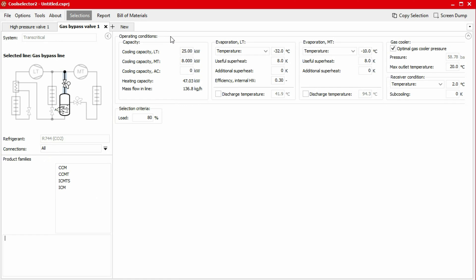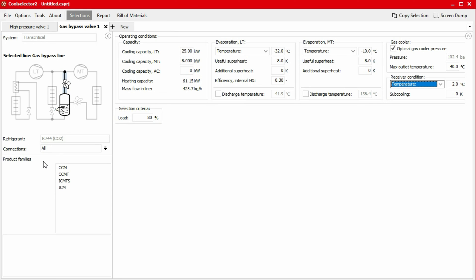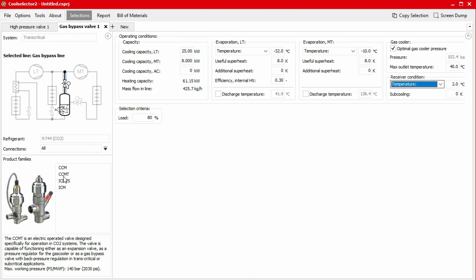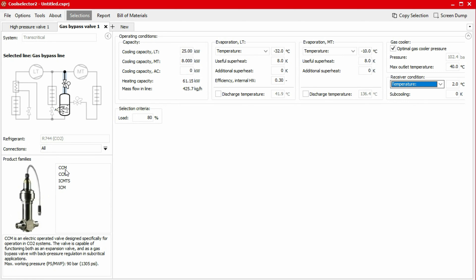Additionally, you can notice that in the case of gas bypass valves, for the gas cooler operating conditions, the maximum outlet temperature is required. The maximum outlet temperature represents the outlet temperature in summer conditions. This is because a higher gas cooler outlet temperature results in a higher opening degree in the gas bypass valve as the gas fraction after the high pressure valve increases. We'll specify the maximum outlet temperature as 40 degrees Celsius for our system in this example. We can then input our selection criteria. The suggested product will be based on how closely it matches the capacity as well as the load percent. For this example, we'll use the default 80% as this gives us some reserve. In the product family section, different options for gas bypass valves are available. We can view a small photo and a brief description by hovering our mouse over each title. In this example, we'll choose a CCM valve.